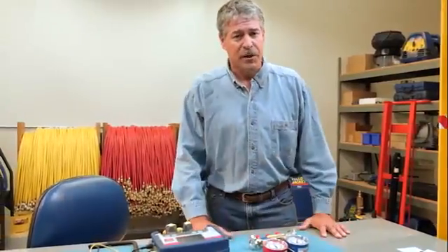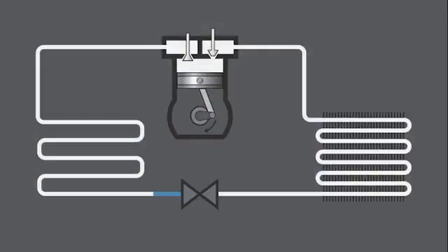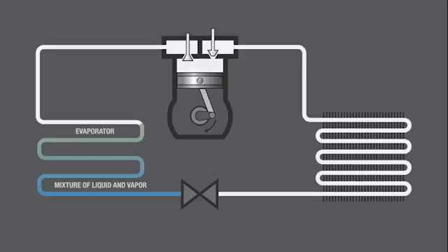First, let's look at superheat. As refrigerant enters the evaporator, it's in a liquid state. As heat is added to the liquid, it will turn to a vapor at its boiling point, or saturation temperature. After the refrigerant has boiled to vapor, any temperature of the vapor above the saturation temperature is the superheat. Superheat is then any temperature of a gas above the boiling point for that liquid.